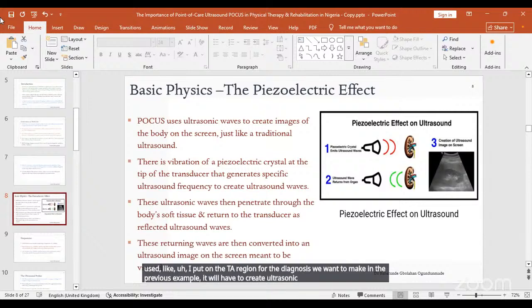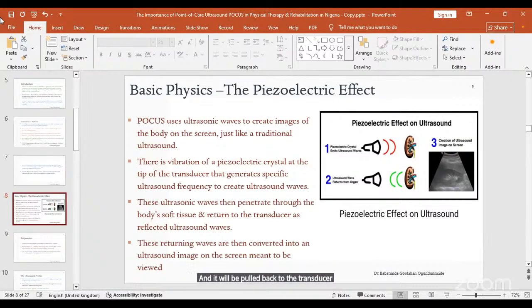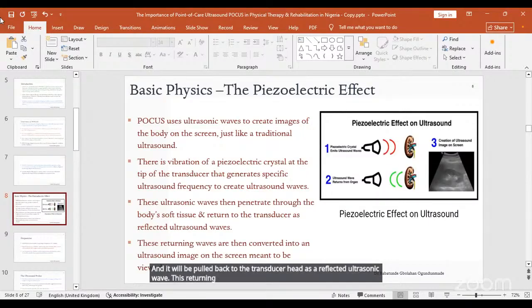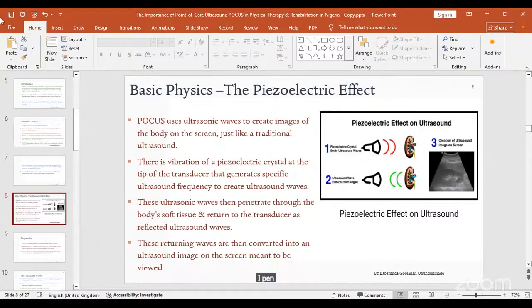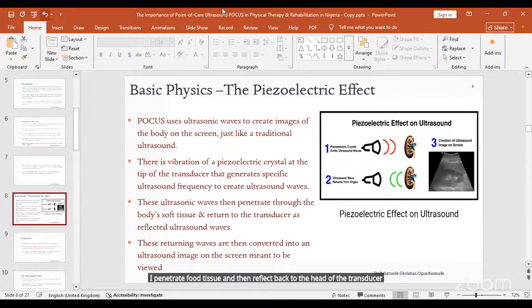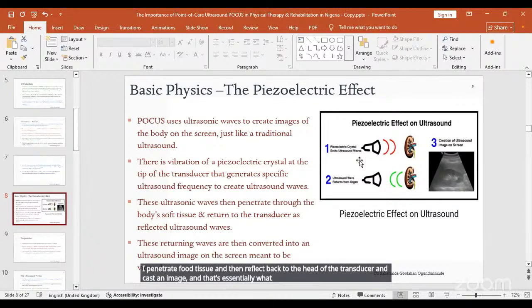ultrasonic waves. And then this ultrasonic signal will penetrate through the soft tissue to the area that is being affected, and it will return back to the transducer head as a reflected ultrasonic wave. These returning waves are the ones that are converted to an ultrasonic image on the screen, and that is what is going to be viewed. It's a simple process like that. Generate ultrasonic waves, penetrate through the tissue, and then reflect back to the head of the transducer and cast an image. And that's essentially what we call the piezoelectric effect.